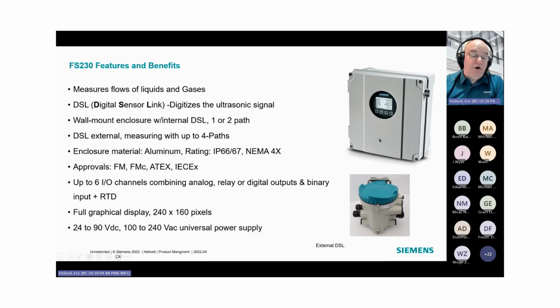The standard 230 comes with a DSL built in, and the digital sensor link is just what takes the information in and converts it into a digital signal so that the internal processors can use it. The 4-path we talked about, IP66. It is FM approved. It also has ATEX, if anybody cares. In the United States, not many do. The standard transmitter itself is a Class 1 Division 2 install. The external DSL is Class 1 Division 1, and the transducers are Class 1 Division 1.